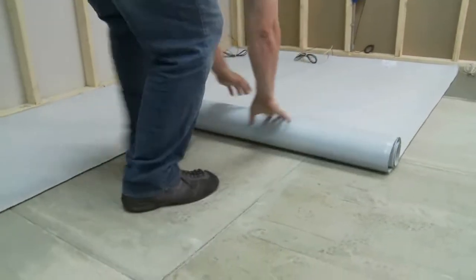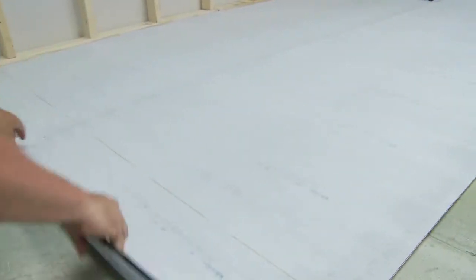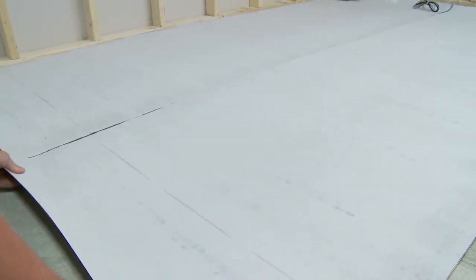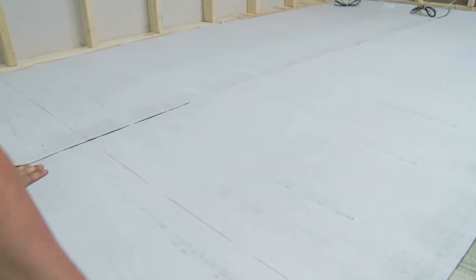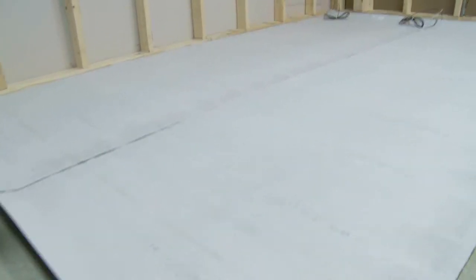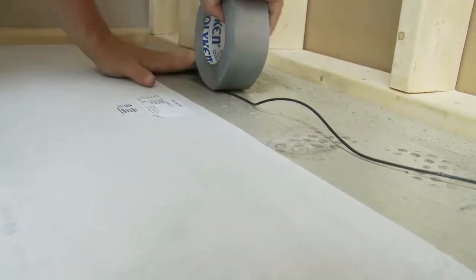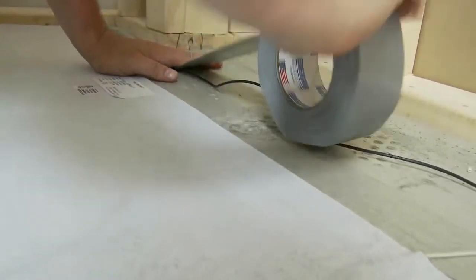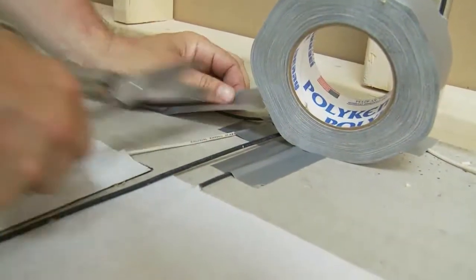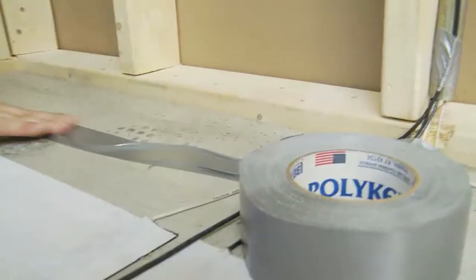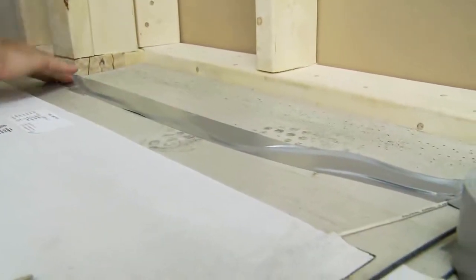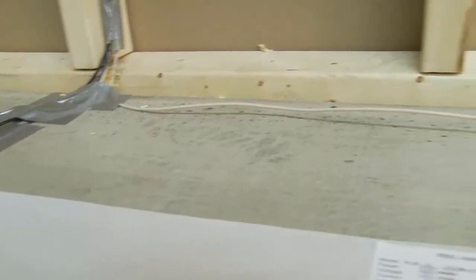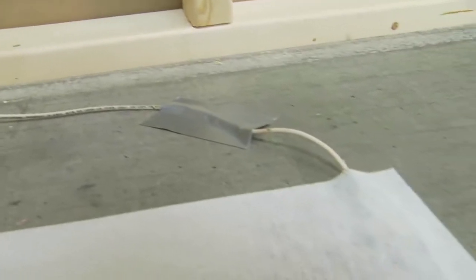Calorique heating panels must be installed so that they will not be covered, even in part, by decorative trim, baseboards, or other structures on the floor. Note: heating panels which are covered by other structures may overheat. Electrical wiring in the floor, other than that for the heating system, must be at least 2 inches away from the heating panels and or separated from the heating panels by insulation or the building structure. Similarly, for heating sources such as hot water pipes, stoves, fireplaces, wood stoves, etc., at least 8 inches of clearance must be maintained. Note: the tile floor heating mats cannot be cut or notched to fit around any obstructions or penetrations, such as door openings or floor registers.